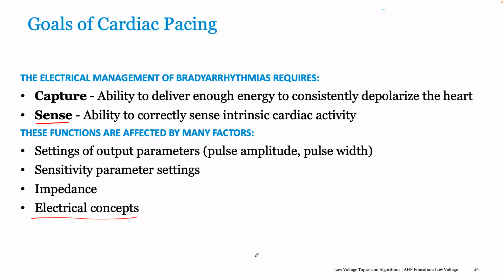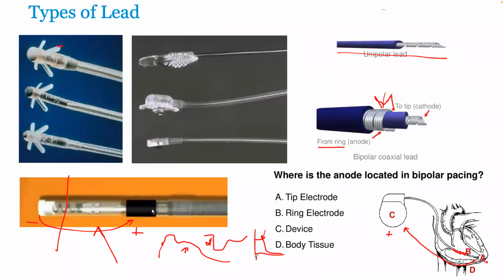Absolutely. I was going to follow up with what Jared was saying with the ST depression as opposed to STEMI for your injury current. And you've both covered it really, really well. But the other thing also, if you've got a half perforation, what we did notice in the patient is that with your sensing of the R wave, you can have respiratory variations, can also have a fluctuation in the R wave sensing as well. So that could also be an indication that there is a slight perforation. For instance, if the anode has gone far beyond and the ring is still in the myocardium itself, as you breathe in and breathe out, you might get some fluctuations in there. And we saw that with an ICD patient a while back.